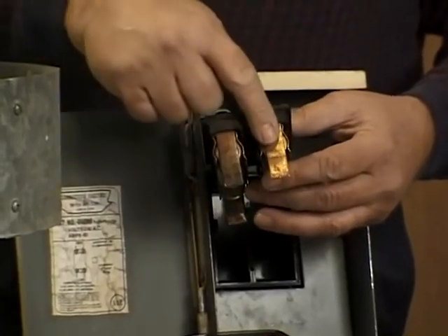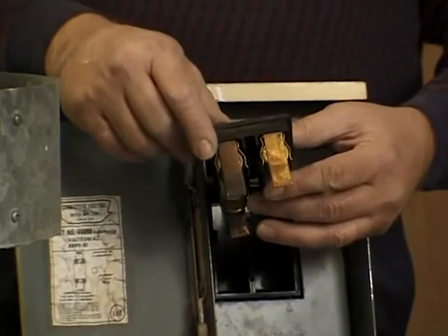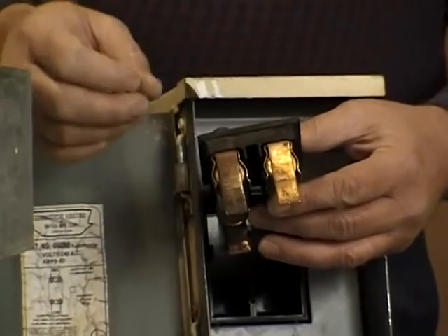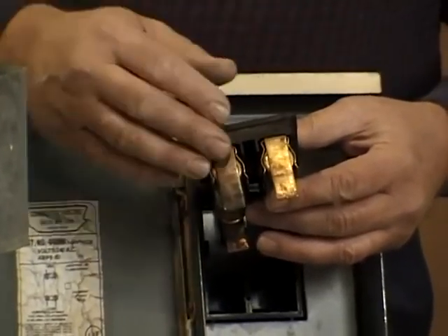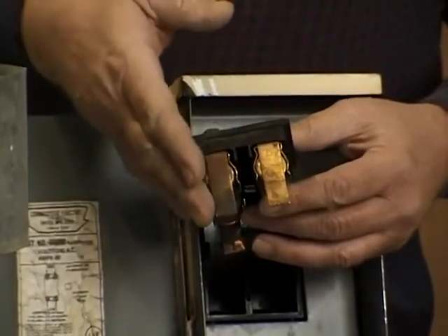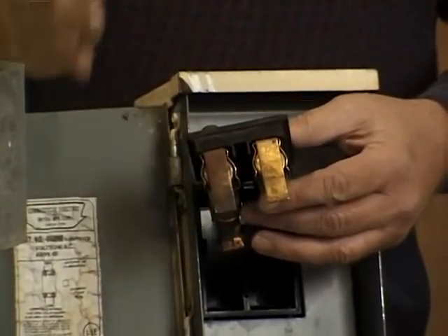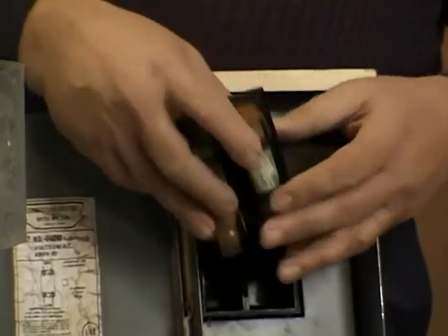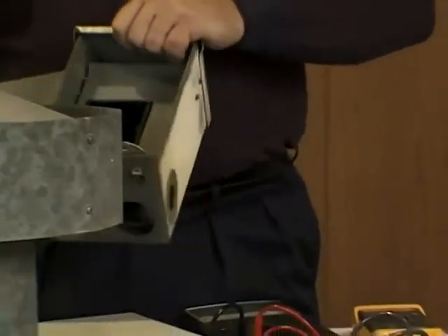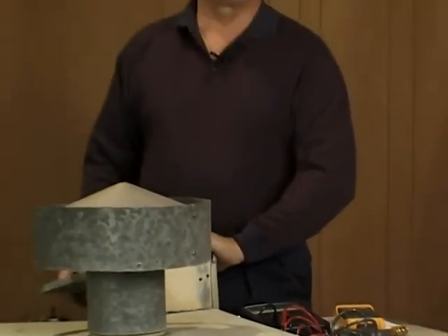We also want to point out this right here. If you take a close look, you'll notice that we have some discoloration on one of these blades. One of the things we want you to be able to look for is that when you see this discoloration, you may have a problem with repeated fuse blowing, and it's not the fault of the equipment at all. So those are the kinds of things and the issues that we want to discuss as we go through this program.